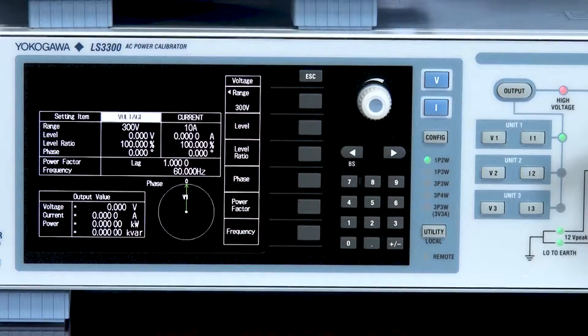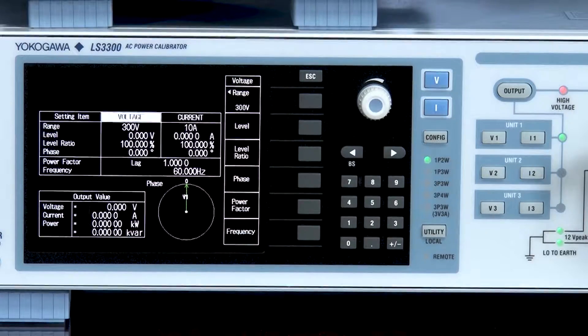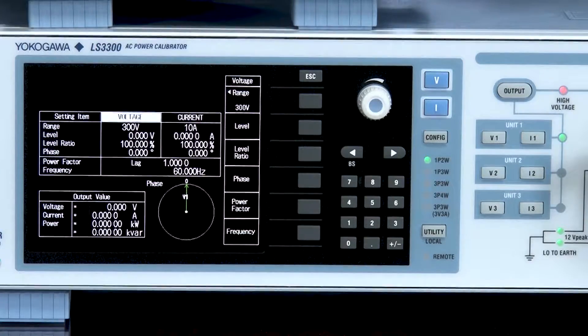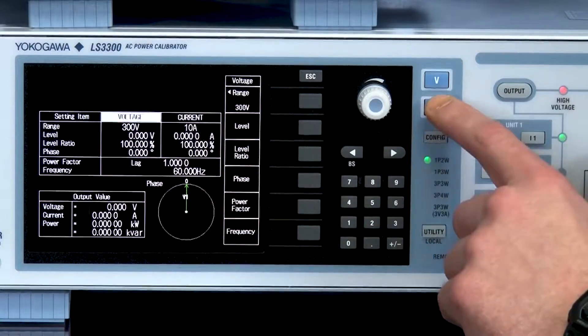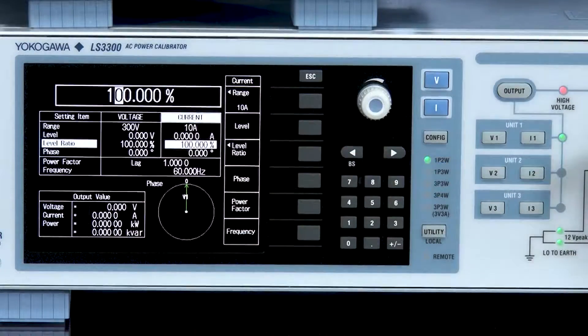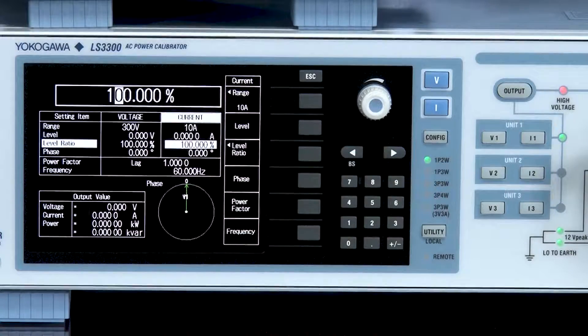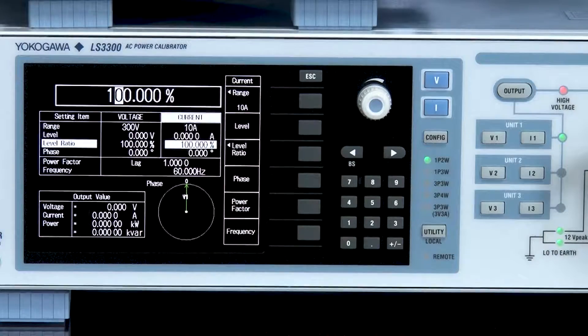We will conduct the accuracy test using the five point method. To perform the five point test we will use the level ratio. The level ratio can be found under voltage or current, which allows you to set the current or voltage level in units of percentage of the range.